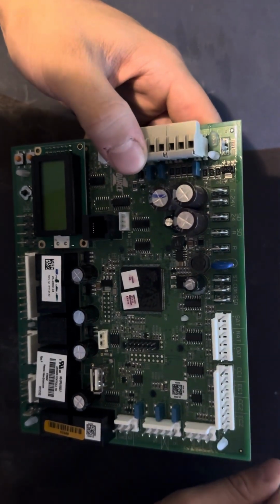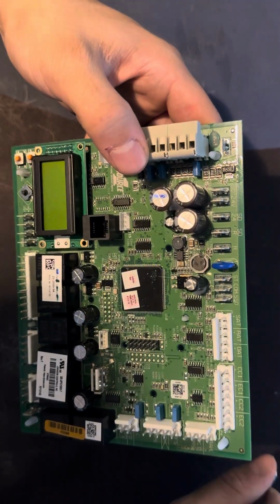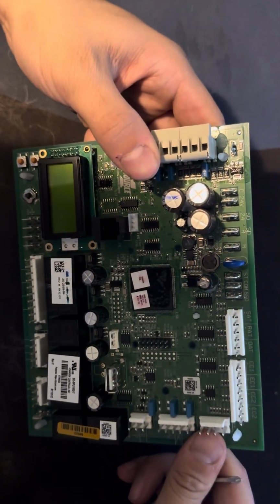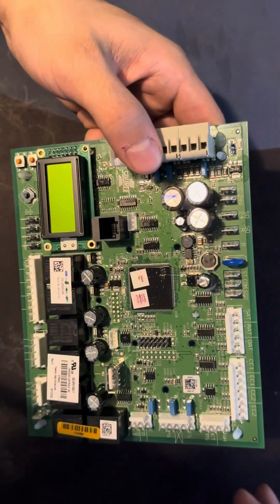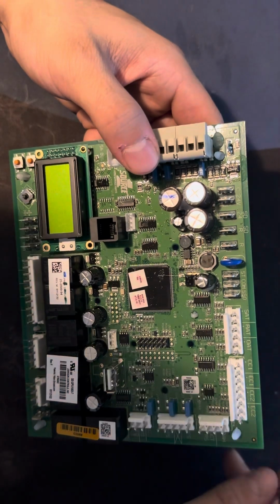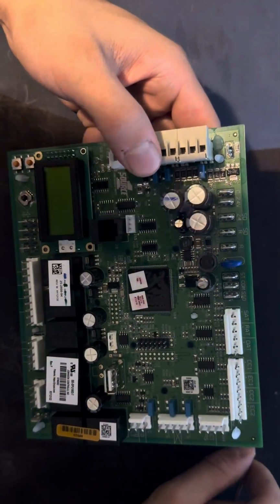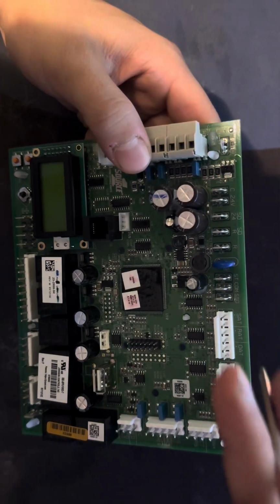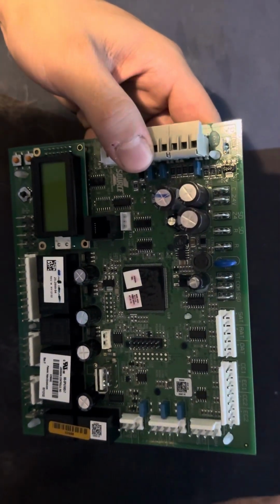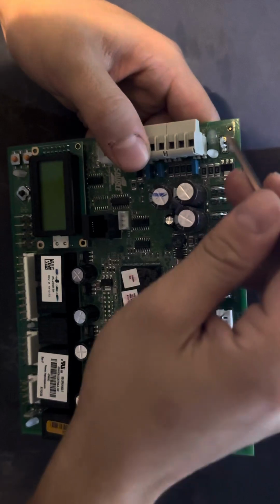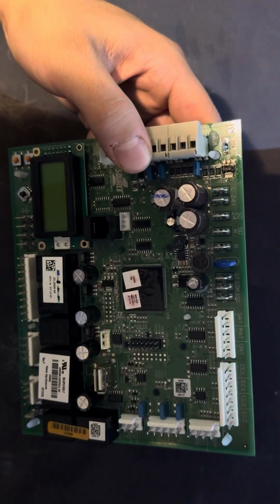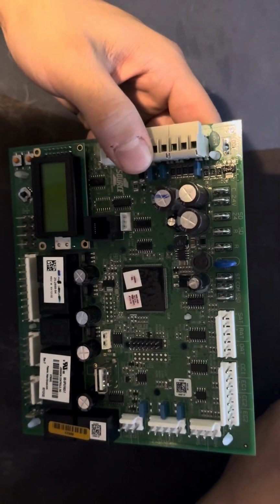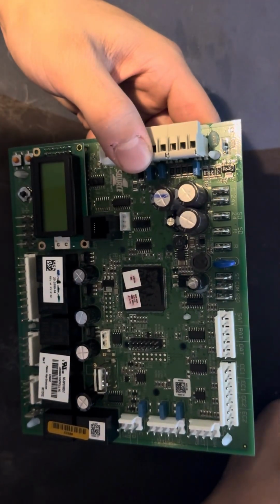Okay, there are some other codes that the board will probably soft lockout on. I think the code was excessive supply air temperature. I'll make a separate video about that just to keep these videos a bit short. Sticking to the HS1 off due to the limit here, this terminal is losing 24 volts 3 times in 1 hour, and it's locking out on HS1, and then it'll hard lock on HS1 off due to the limit.